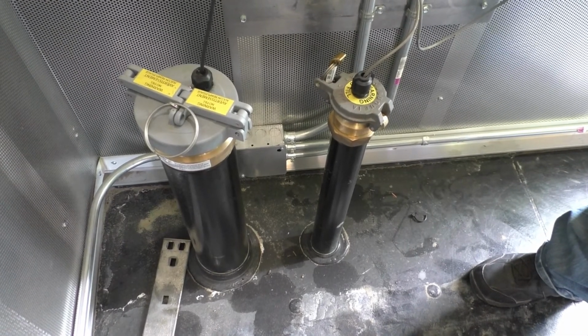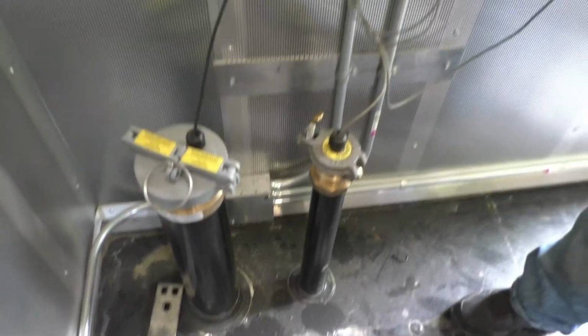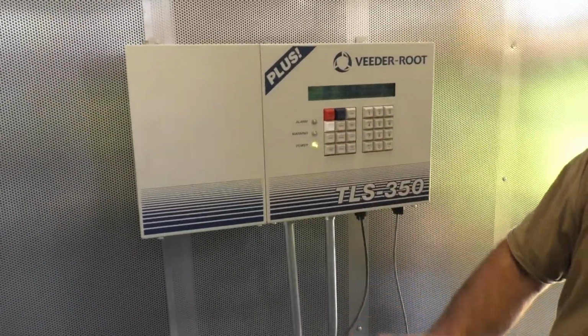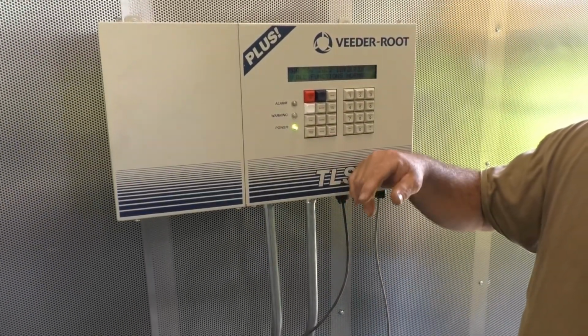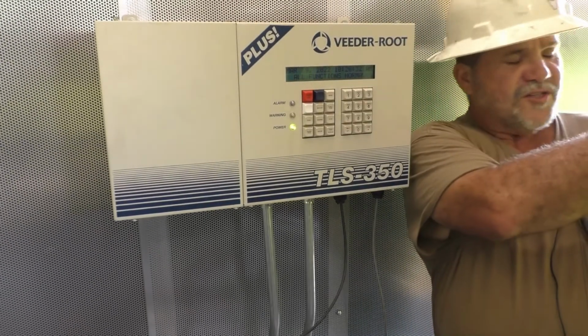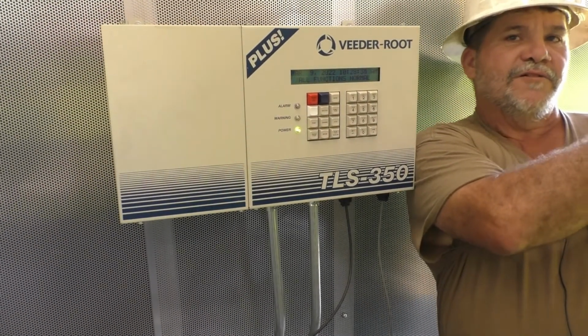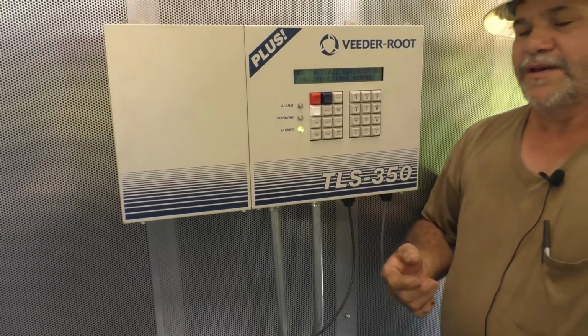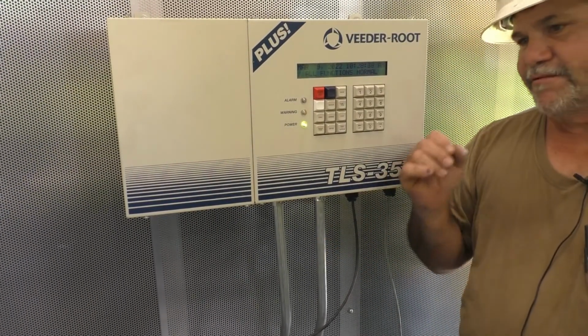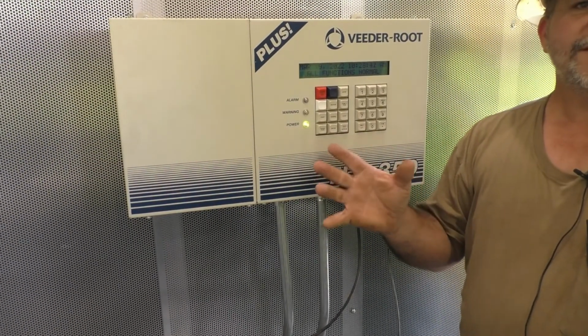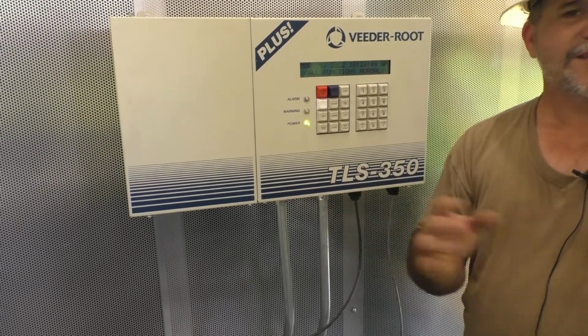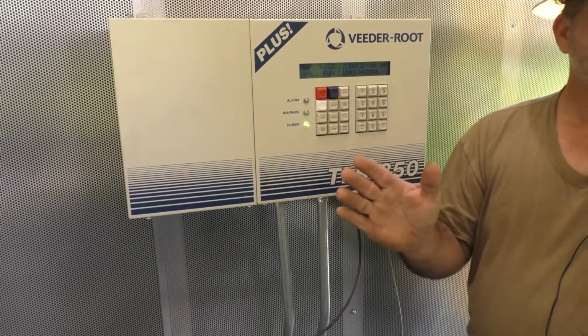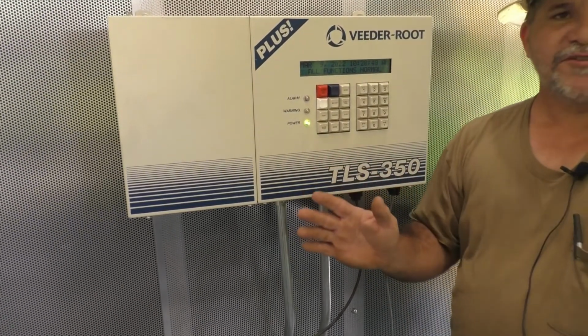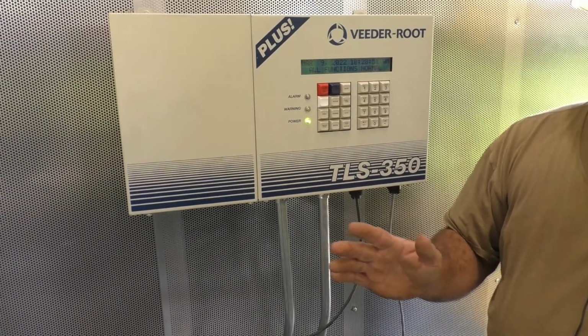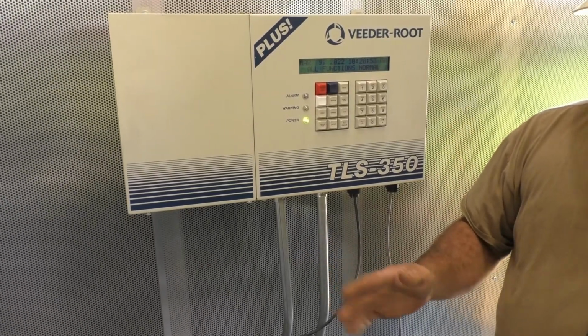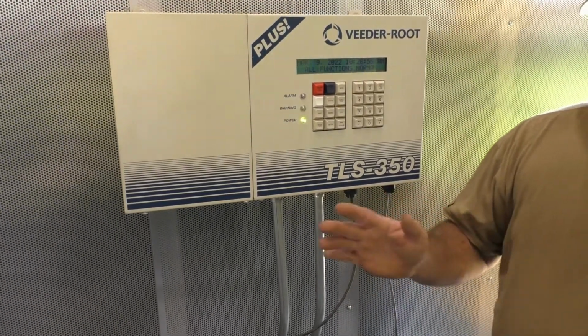If you get an overfill condition, that's at 90% of the tank volume. It will go into an overfill. The external alarm on the outside of the enclosure will go into alarm. Right now it's set so it'll buzz loudly for about 1 second and shut up. We're going to extend that to whatever y'all want it to be. I promise you, you don't want to be the fuel driver and don't want it to be long. I can promise you, he's right there by it. But it'll get his attention.